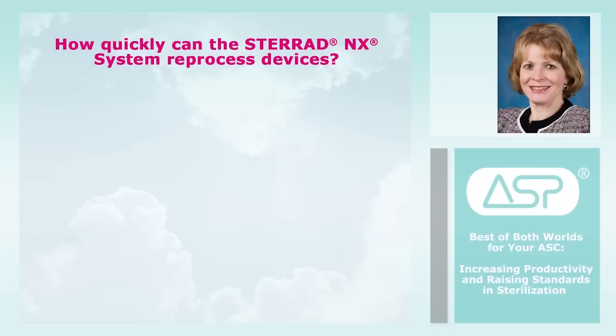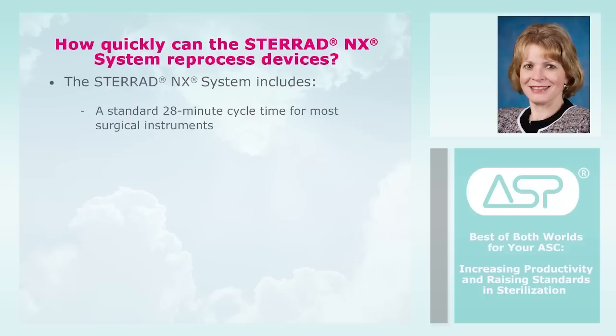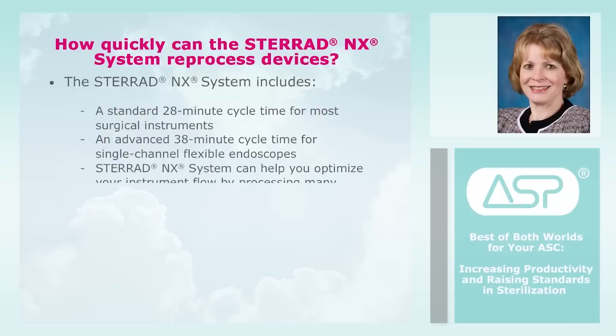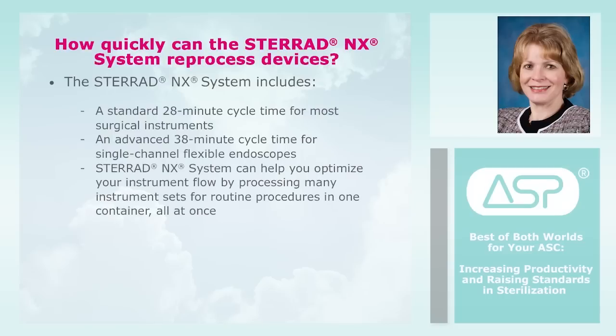Next question is, how quickly can the STERRAD NX system reprocess devices? The STERRAD NX system has a 28-minute cycle time to help ensure a fast instrument turnaround. There is also an advanced 38-minute cycle time for single-channel flexible endoscopes. In addition, the STERRAD NX system can help you optimize your instrument flow by processing typical rigid scopes, bridges, sheaths, forceps, and light cords required to perform a routine procedure in one container all at once.